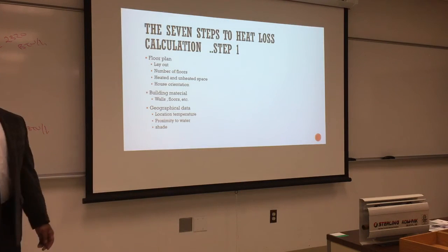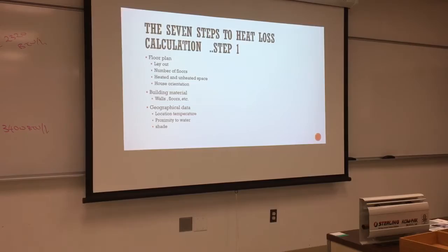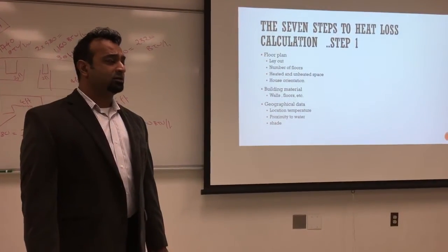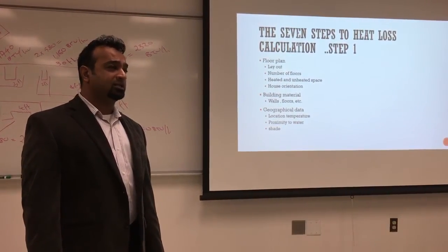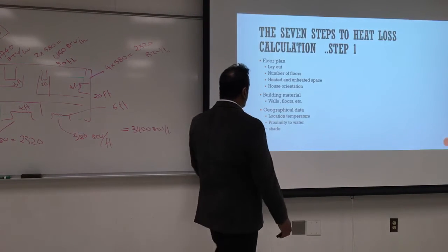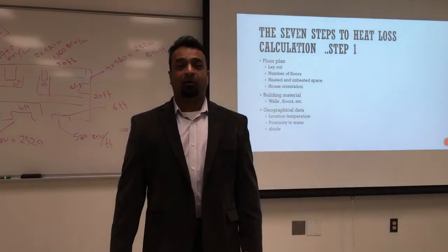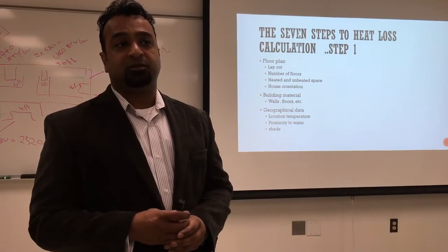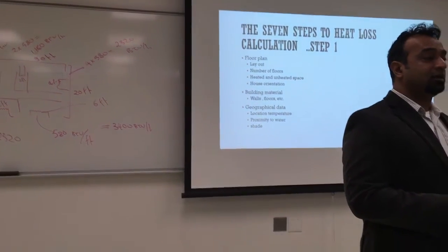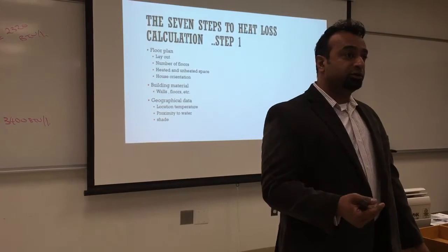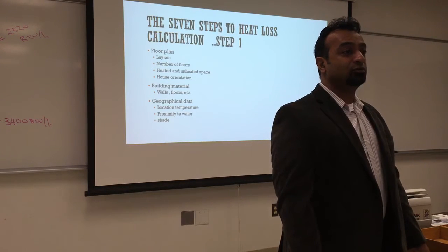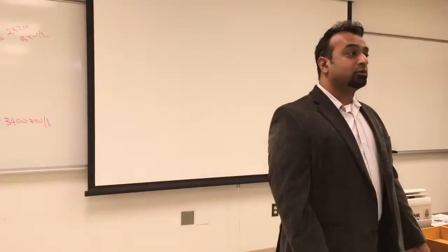Geographical data: get the location's temperature—the coldest day of the year for heating, and now also the hottest day of the year for cooling. For Springfield, the coldest day is zero Fahrenheit and the hottest goes to about 105–110°F, and that has been changing with more hot days. Also consider proximity to water—do you live by a pond, ocean, or lake? That affects your cooling load because you have to calculate humidity. If it's too humid, the AC has to dehumidify before it can cool, taking many extra BTUs.